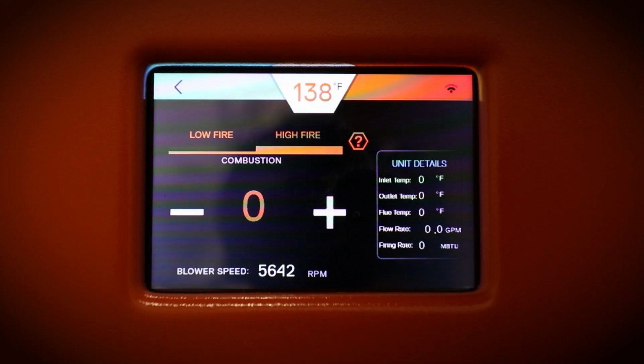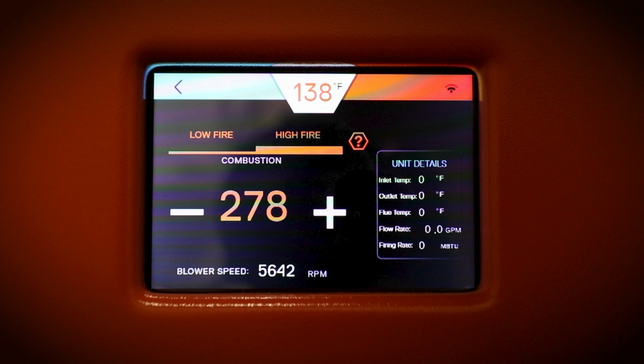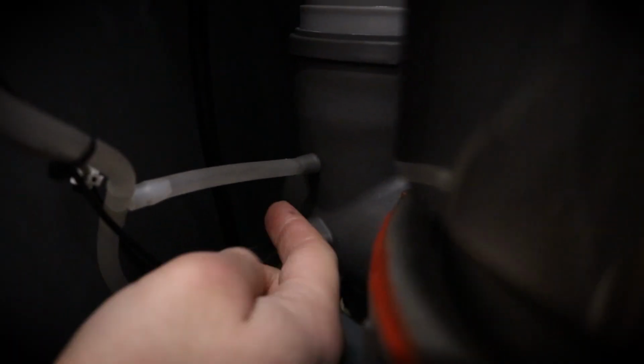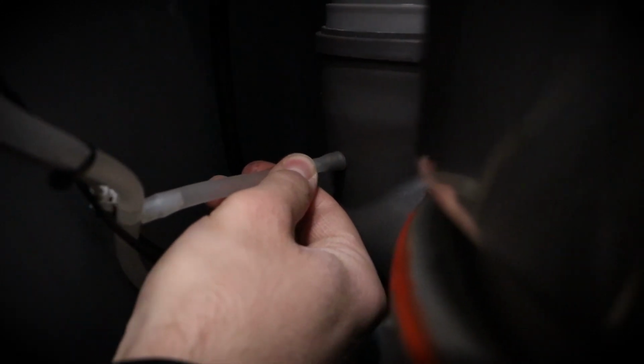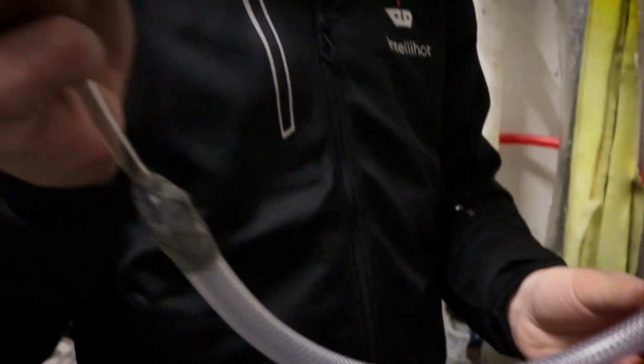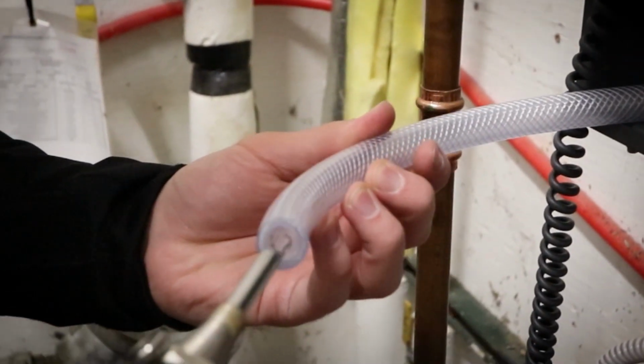Calibrate your combustion analyzer to the fuel type of your unit, either natural gas or propane. Locate the air switch ports on the side cast of the heat exchanger. Remove the top port and place a piece of tubing onto the port. Place the analyzer probe into the opening on the other end of the tubing. Note, drilling a hole in the exhaust manifold will void the warranty of the unit.